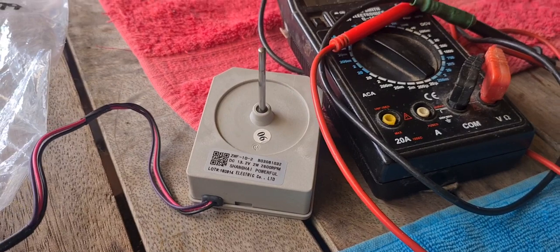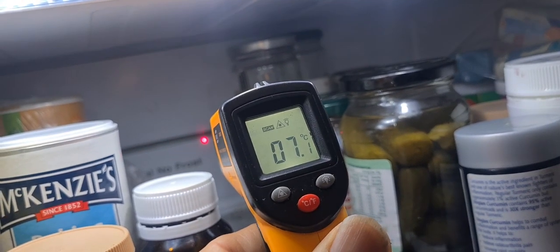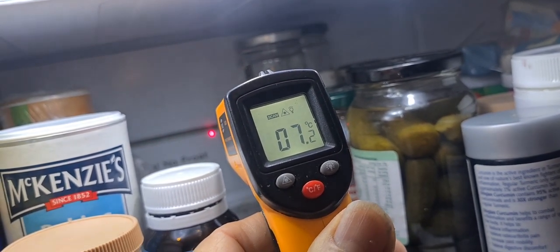Anyway, put in your new motor in the fridge and it's up and running. Let's see if we are getting cool in here — oh yes, we're down to seven degrees. That's good because I've set it to four on the outside, so if it gets all the way down to seven I'm a happy camper. There we go.